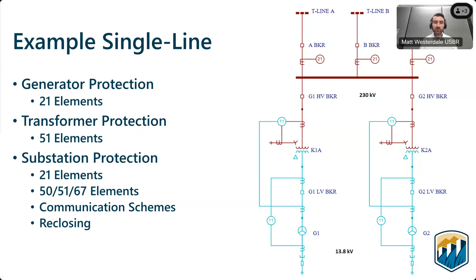In our example, we're replacing a generator step-up transformer to account for a rewind and uprate on one of our generators. Because we're increasing our generator size, we need a new transformer, and this means we have new nameplate and test data that we need to communicate to our TO because they need to update their short circuit model.